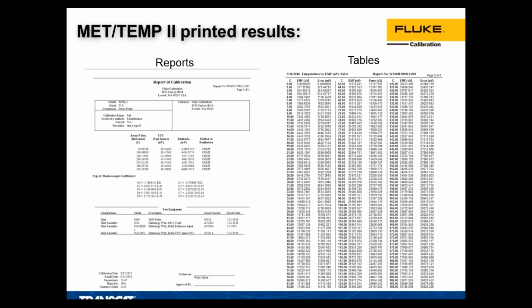If you take enough calibration points, those residuals will be a great quality check to tell you if something looks wrong with the curve, and maybe something got messed up. Maybe go back and check a point or two. In some cases, you might have to redo a calibration if you catch a mistake. But without some analytical check like that, you may never even know there was a problem with the calibration.